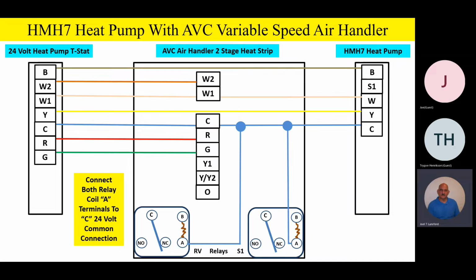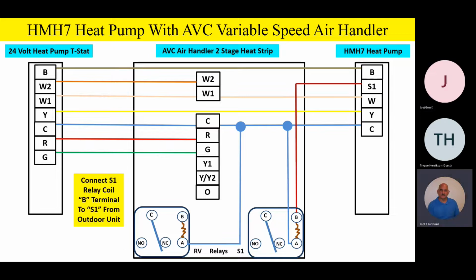So both relays, one side of both relay coils, we'll call them the A terminals in this example, both relay coil A terminals are going to go to 24-volt common. So that's our common terminal for both relay coils. The B terminal, or the other side of the 24-volt relay coil on the S1 relay, goes up to S1. That's kind of why we call it the S1 relay. So that's going to be energizing that relay that we've looked at before. It's essentially the same wiring.